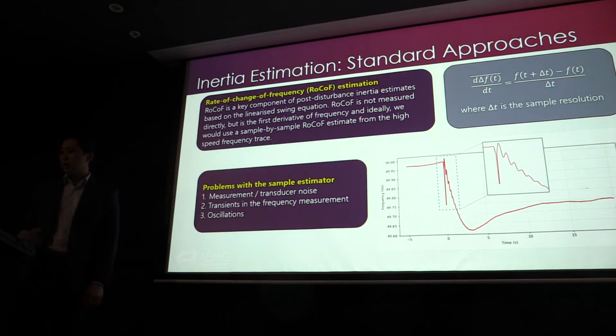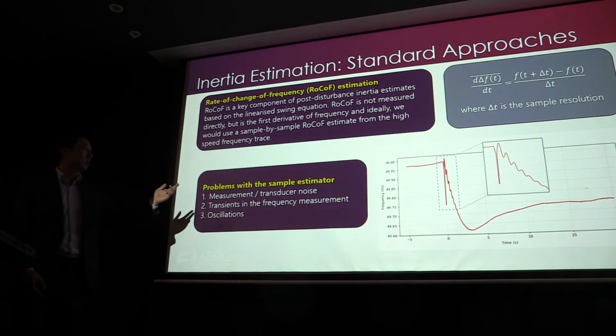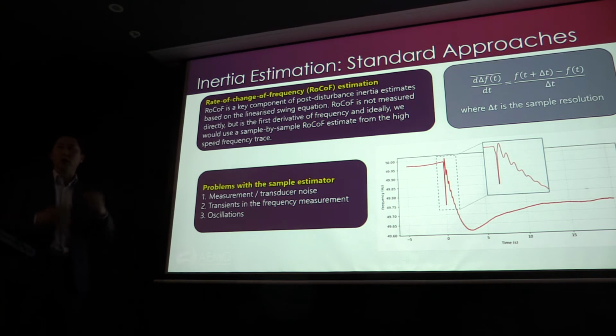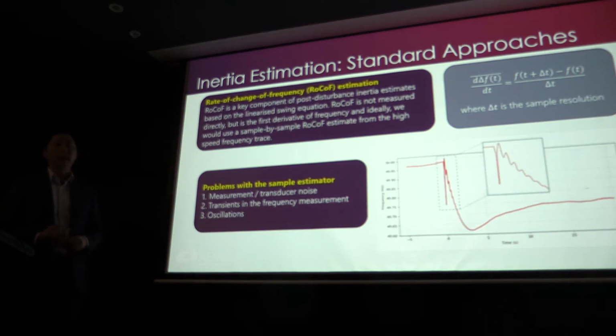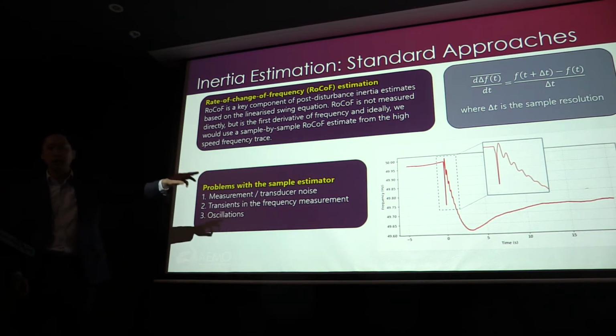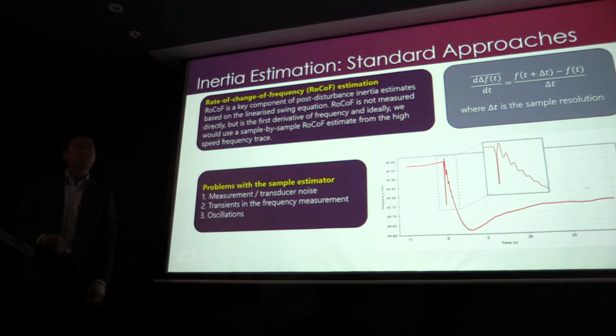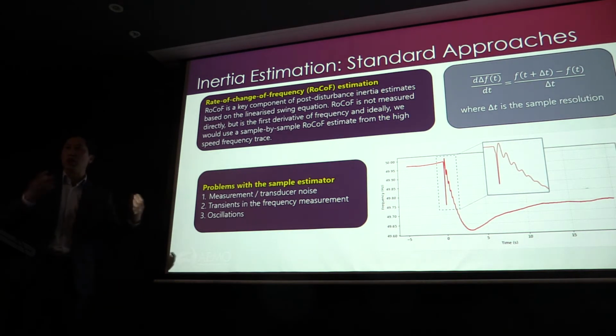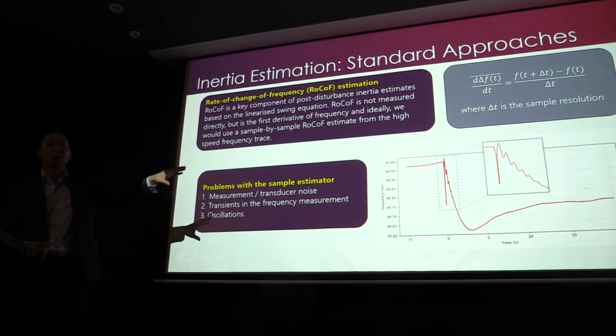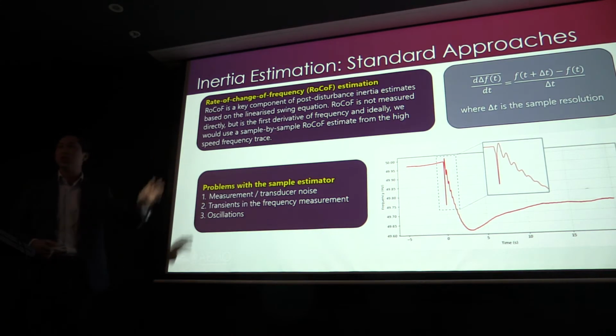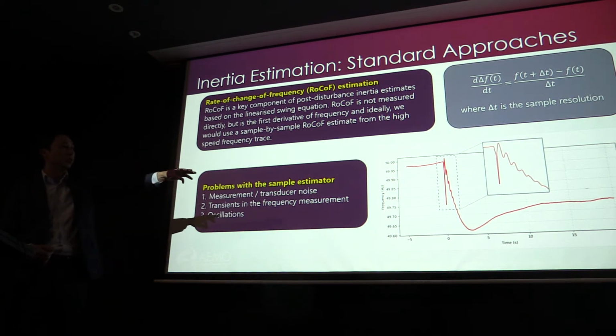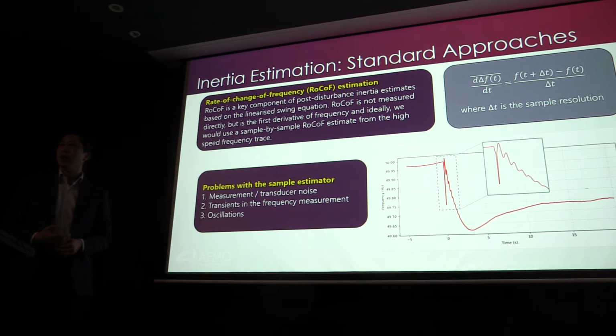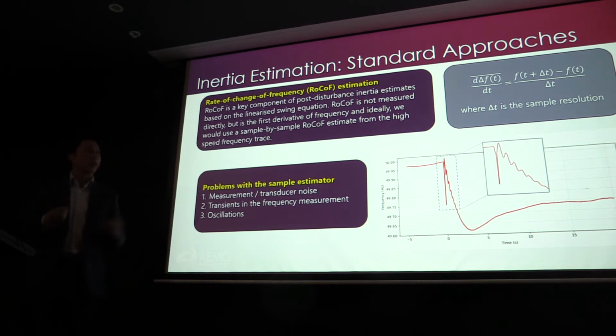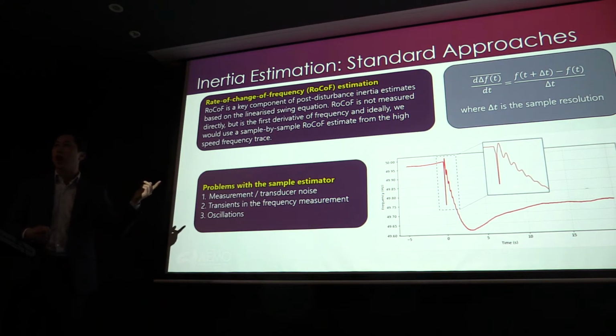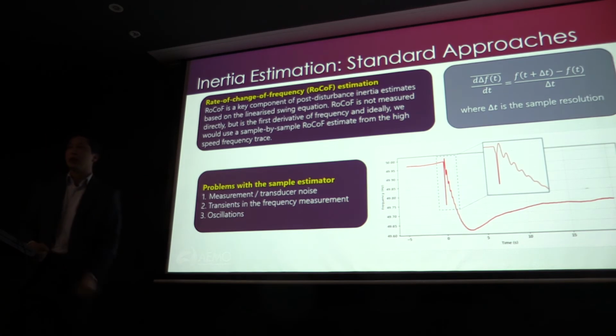But unfortunately, there are quite a few problems with that sample estimate, not least the noise that you get from the transducer. You'll end up with a lot of spurious numbers coming out of that estimate. Secondly, you might even have transients in the frequency trace, maybe because of a network fault. And thirdly, you might have oscillations from generators oscillating against each other. So your frequency trace is not clean, and often you have all these different features in it. If you tried to use that, all of a sudden you'd think you'd had a RoCoF of like 4 hertz per second. Incidentally, this is why a lot of protection relays trip on RoCoF: they think the rate of change of frequency is a lot higher than it actually is, because they're trying to do these estimates in real time.